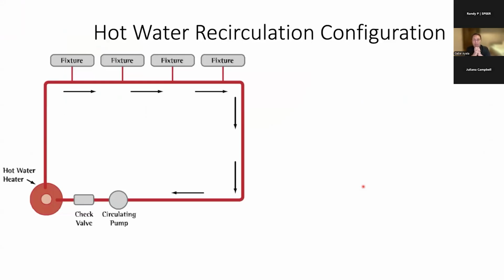Let's talk about hot water recirculation configuration. It's not just about the control of the pump that's important for a high performing hot water system. You also have to really follow some guidelines as far as how to run the plumbing and how to design the recirculation loop. Generally speaking, the recirculation line, or we call it the trunk line, should be no more than about 3/4 inch in diameter. And I know that IAPMO is considering reducing this to maybe even 1/2 inch. But certainly no more than 3/4 inch.